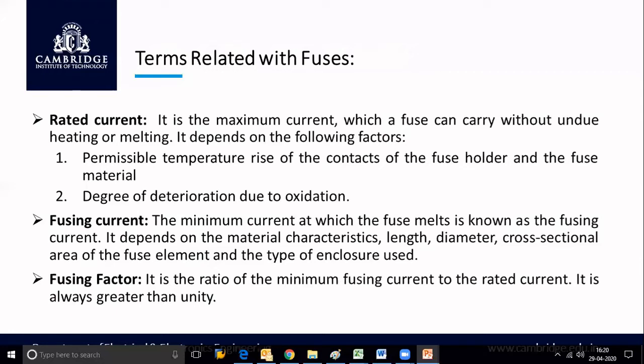And it depends upon the following factors. The first one is the permissible temperature rise of the contacts of the fuse holder and the fuse material, and the degree of deterioration due to oxidation. So keeping these factors in mind, we have to decide the rated current of a fuse. Rated current of a fuse means the maximum current the fuse can carry without melting. Next, what is meant by fusing current? The minimum current at which the fuse melts is known as fusing current.